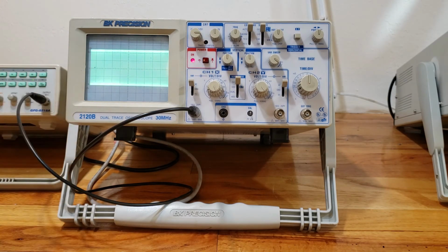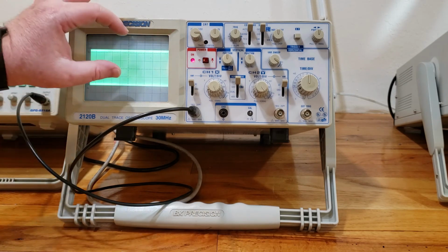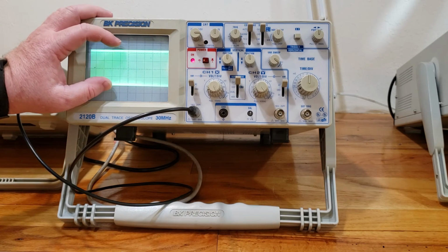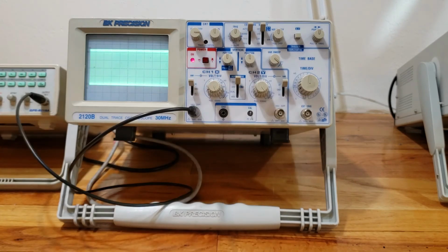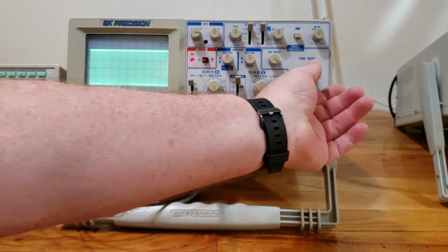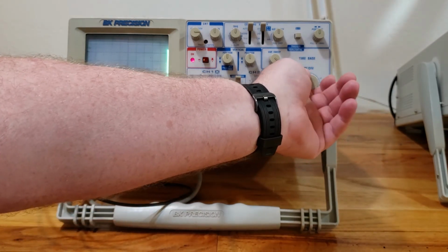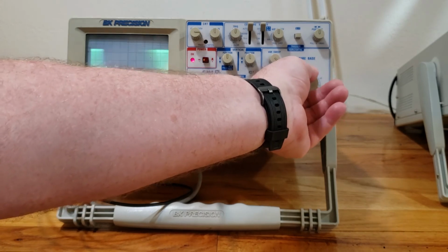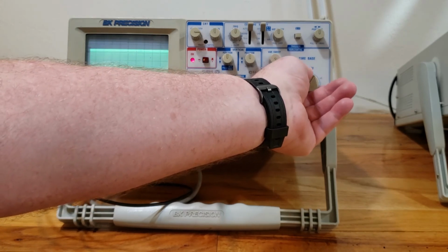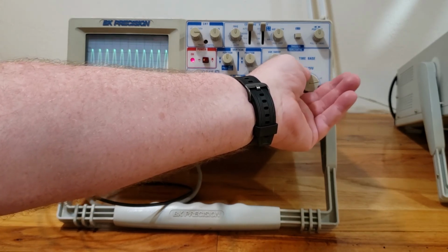All right. Now that I have it set to this point, the next thing I'm going to do is adjust the time division. Once I get the volt division set where I can see both top and bottom of the trace, I use the time division knob. I'm going to adjust one way or the other. Okay, that doesn't seem to be helping very much, so we must need to go back the other way. Let's keep going here. There we go. Now we're starting to see something.